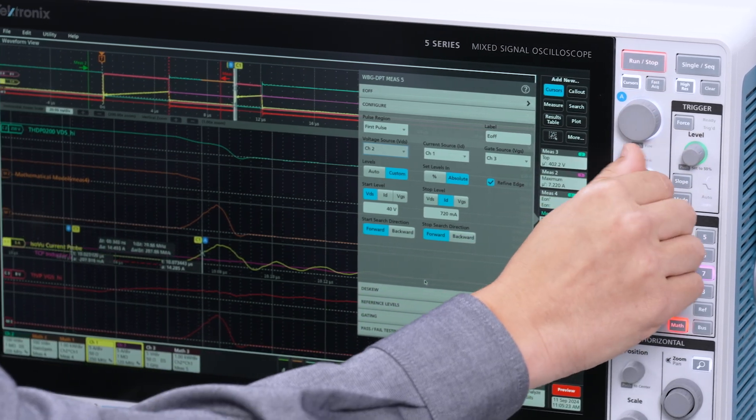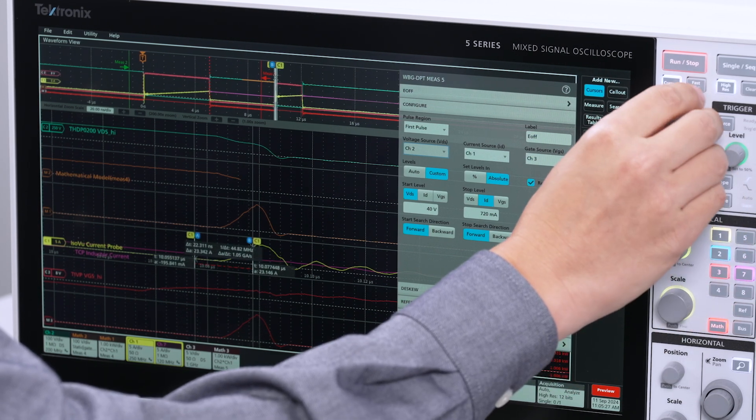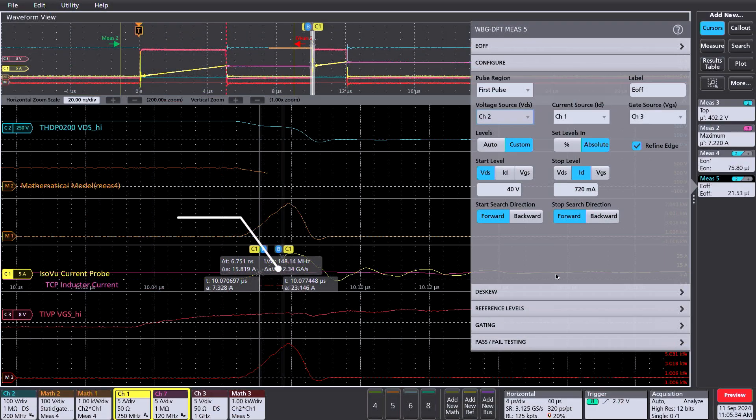Now that we have this measurement, there are a few other interesting parameters to look at. One is DI/DT — how quickly the load current is changing during turn-on. Quickly using the cursors, I can go to the steepest part of the current waveform. The cursor readout shows me 2.3 gigaamps per second, which is equivalent to 2.3 amps per nanosecond. DI/DT can be seen accurately for the first time thanks to the IsoVu current probe. This parameter is key with motor drive applications — if you have DI/DTs that are too large, you can saturate the motor core and reduce efficiency.